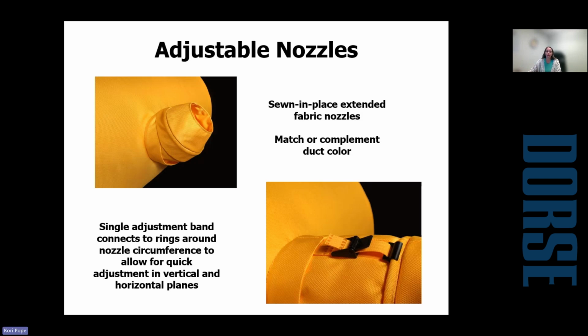So we use these in a Toyota manufacturing facility in Kentucky, where the assembly line workers were complaining that one was too hot, one's too cold, one's getting too much air, and so on and so forth. So what we did is we took fabric duct, we dropped it off of the metal ductwork at each line station, and we put one of these adjustable nozzles there on the end of the duct, so that at each station, each employee was able to adjust how much air they were getting, as well as where that air was blowing, to provide maximum comfort to those employees.